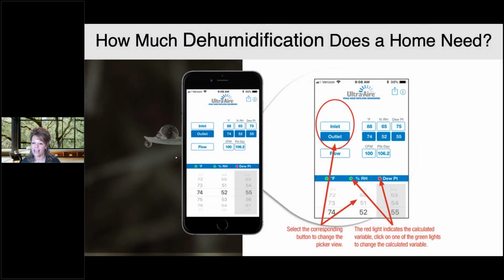We do have a resource. It's still branded Ultra Air because the amount of money to update this app is astronomical. What this allows you to do is enter the inlet, which is the conditions outside. So it's 88 degrees, with a 75-degree dew point outside. Inside, I want 74 degrees, which is the outlet: 74 degrees, 52% RH, and a 55-degree dew point. The flow is my ventilation number. Based on these inputs, you're going to need 106 pints a day of dehumidification just based on your ventilation.